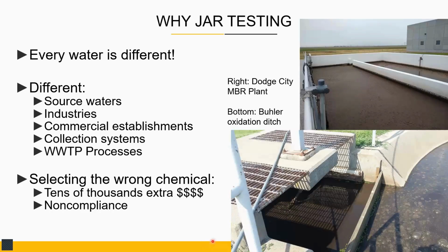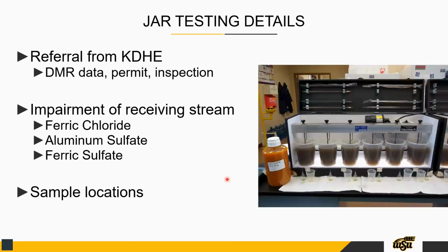Do the diligence there. I have found in jar testing and in some real world experience that there are some chemicals that won't work at some plants. So you don't just make that assumption. And some chemicals are far less economically efficient. So jar testing looks like this.